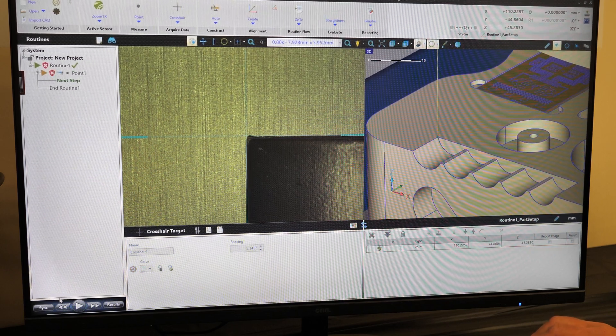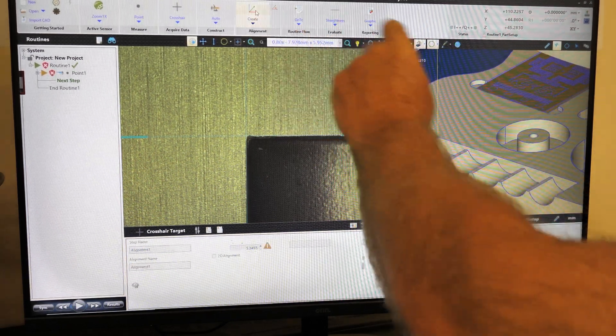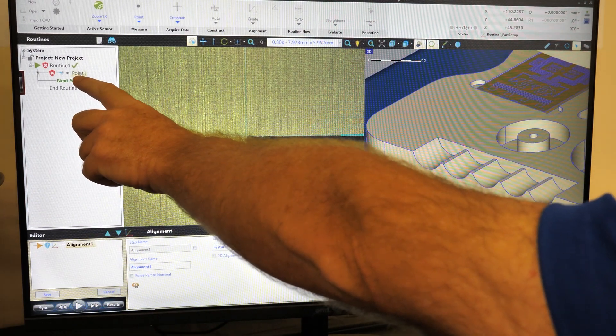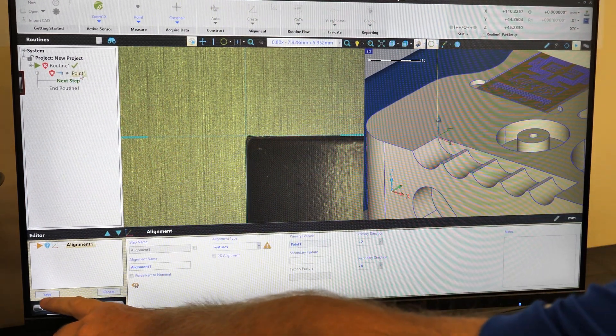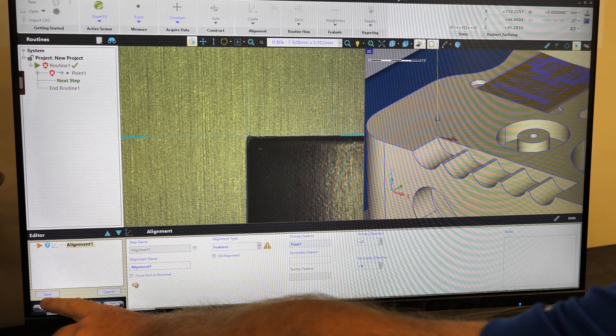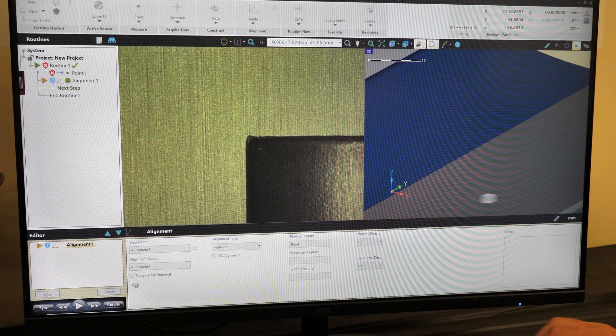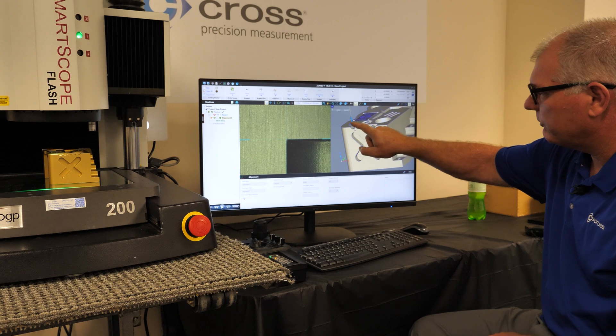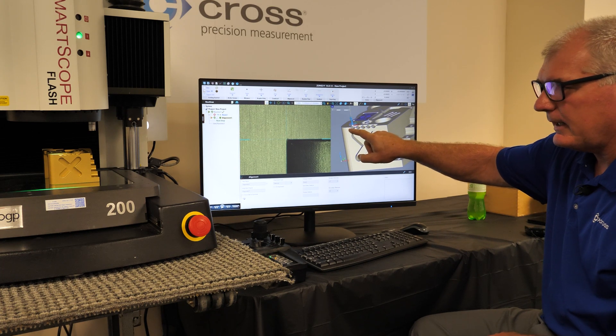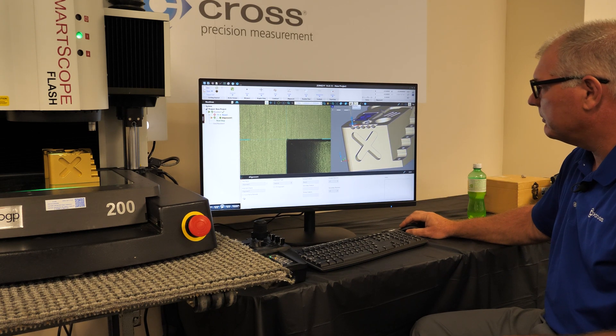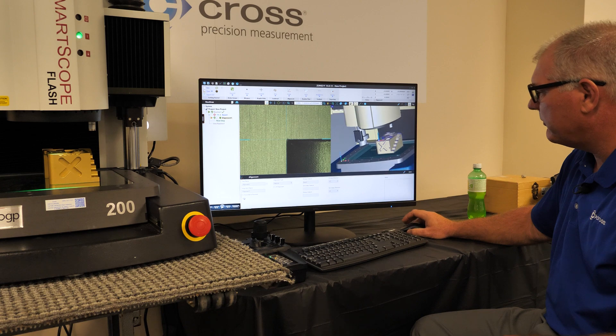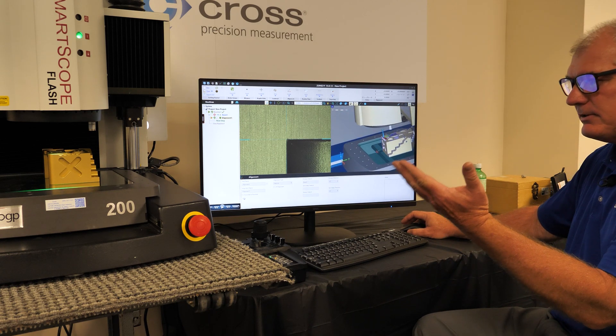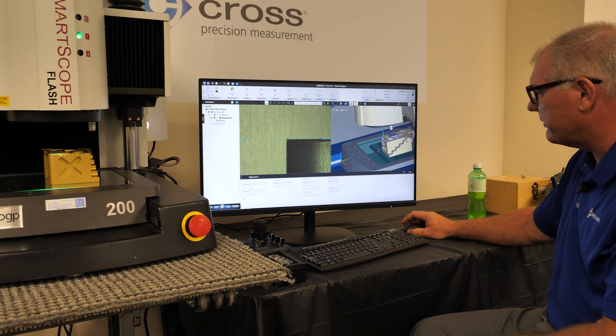We can create our temporary alignment on point number one and select Save. If we look at the screen, we see the blue box on the CAD model, which represents the camera. I'll turn the machine back on, and now we can see the part has actually shifted into the machine — so it matches exactly what is on the stage.